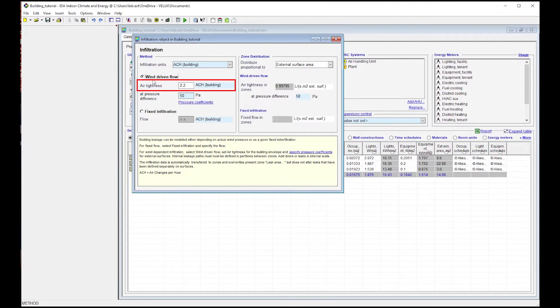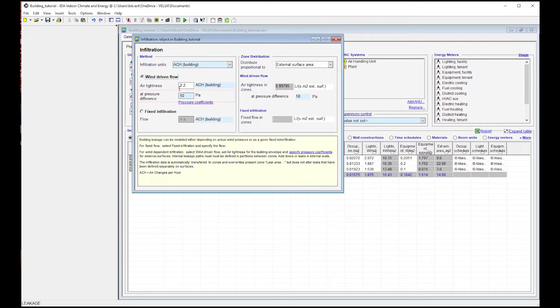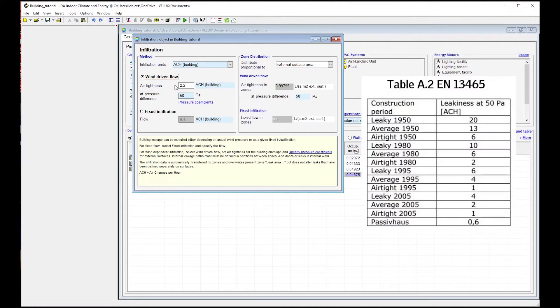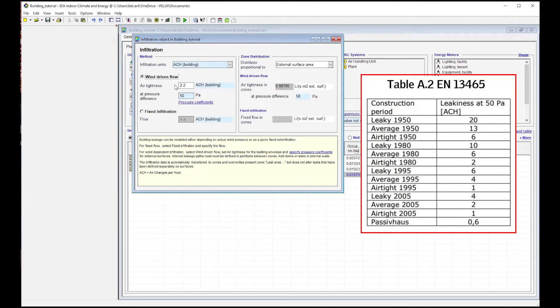To use wind-driven infiltration, you need to set the air tightness of the building, which is usually given by an air change rate at a given pressure difference, often 50 Pascal, between indoors and outdoors. If you have carried out a blower door test on your building, you can input the results here. Otherwise, the following table provides infiltration rate values measured in air changes per hour at 50 Pascal according to the construction period. In case you prefer to use the fixed infiltration mode, note that it is calculated at 4 Pascal of pressure difference.